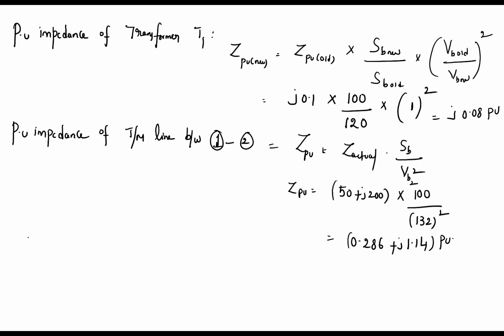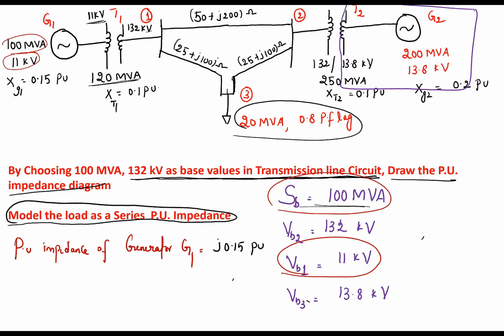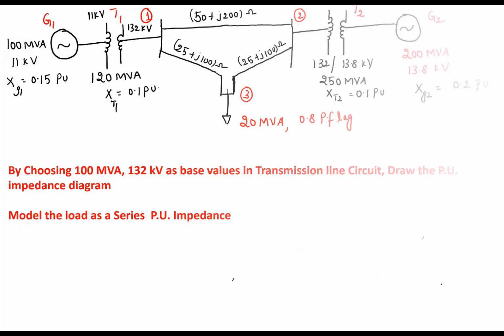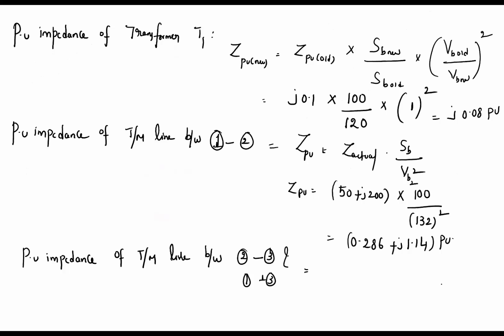Similarly, if you calculate the per unit impedance of the transmission lines between 2 and 3 and 1 and 3, why am I doing them at a time? Because both values are the same, 25 plus J100, 25 plus J100. So I am doing them at a time. Again we use the same formula, Z actual divided by Z base. So it will become 25 plus J50... sorry, 25 plus J100 into base MVA 100, base voltage of the transmission line 132 kV whole square. This value will be exactly half of the previous value, because only the base impedance value is becoming half. So you are going to get 0.143 plus J 0.57 per unit. Like this, we have calculated the per unit impedance of the transmission lines.